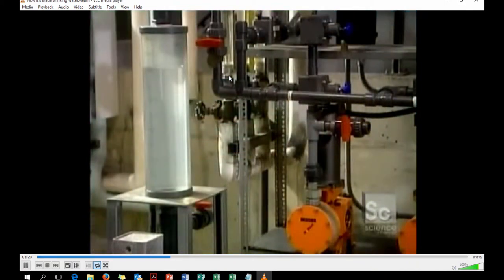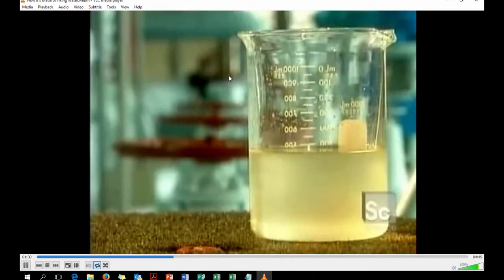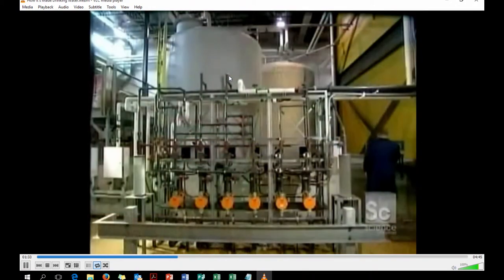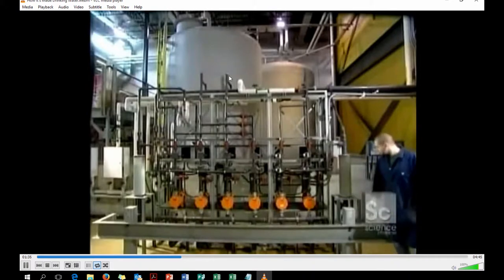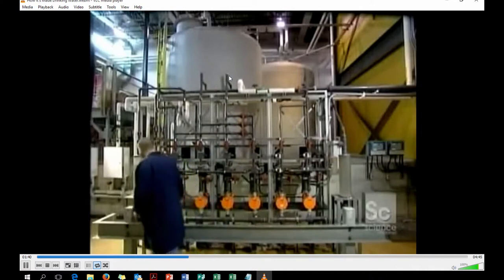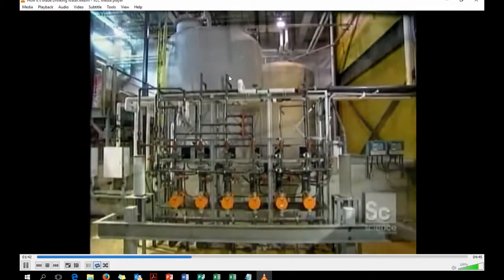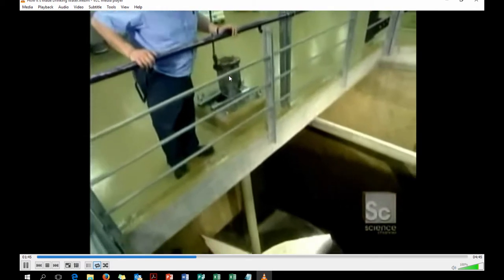They first add a powerful form of the chemical element carbon called activated carbon. It absorbs contaminants such as solvents and pesticides, and rids the water of bad taste and odor. From there, the water goes through a series of mixing tanks. The first tank holds a chemical called aluminum sulfate. It acts as a coagulant, a substance that thickens liquid into globs. In the raw water, the aluminum sulfate forms tiny sticky globs called floc.